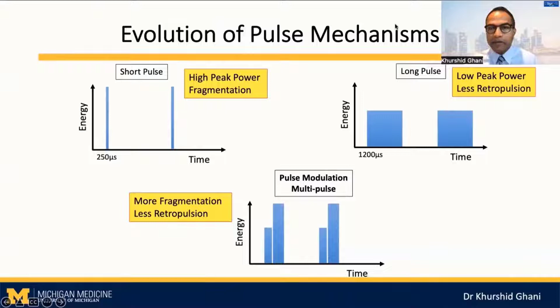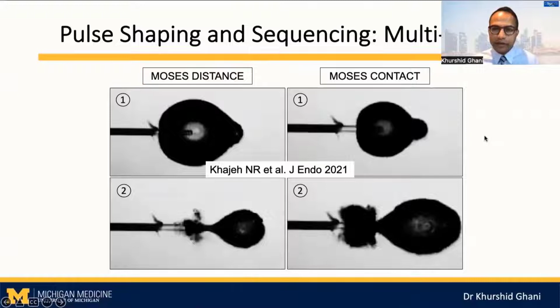And this is what Moses pulse looks like under high-speed imaging. There are 2 types of Moses pulses available with the Moses technology platform from Boston Scientific. One is Moses distance and one is Moses contact. And you can see the bubble profiles of this split pulse in these sequences here. This is a simpler schematic just to show the difference between the 2 pulses. And the main thing to understand is that the Moses distance pulse has 2 equally weighted large pulses compared to the Moses contact pulse, where the first pulse is a bit smaller in profile, followed by a second larger pulse. And these differences in the weighting and the sequencing of the pulses will have different impact on fragmentation.